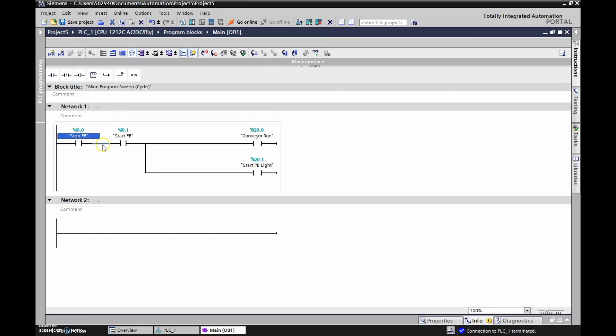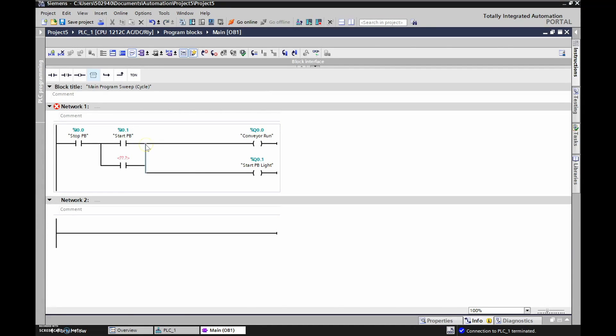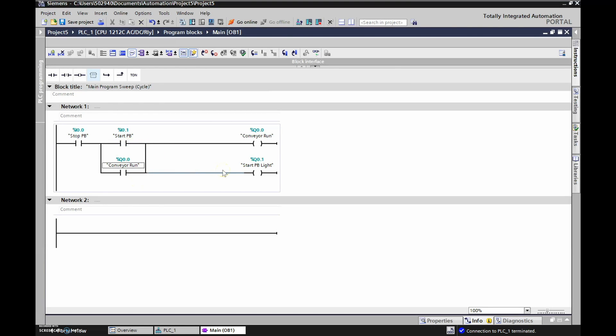In addition to the start push button, we need to do three-wire control. Three-wire control consists of another contact in parallel with your initiating switch — the start push button. We're going to add another rung, add an XIC, and bring it up to tie in, creating a parallel branch. We'll address this the same as q0.0. Double click, scroll down until we see that tag, double left click outside and it cleans up the ladder diagram. Now we've got three-wire control: a start, a stop, and a holding contact, plus the two outputs — conveyor run and start light.